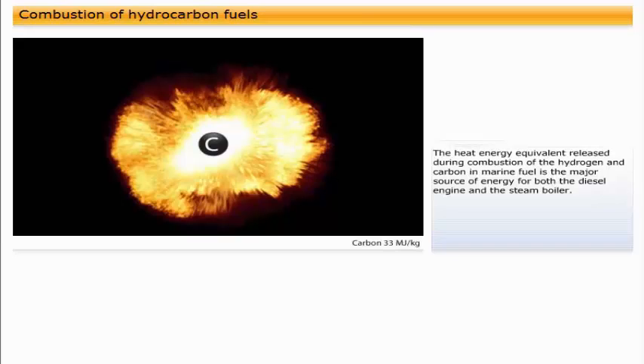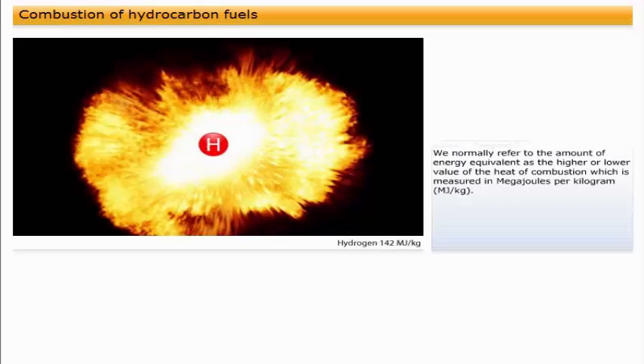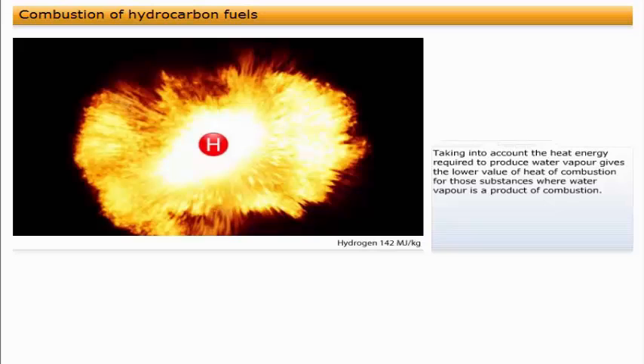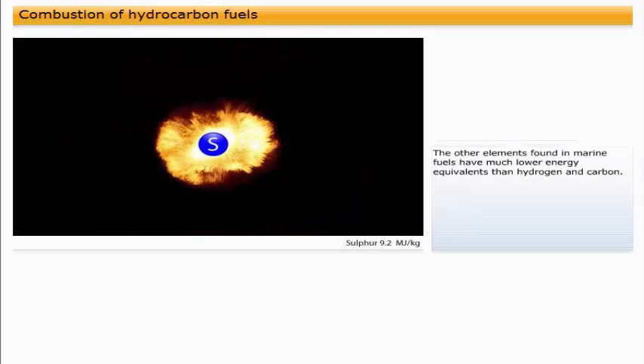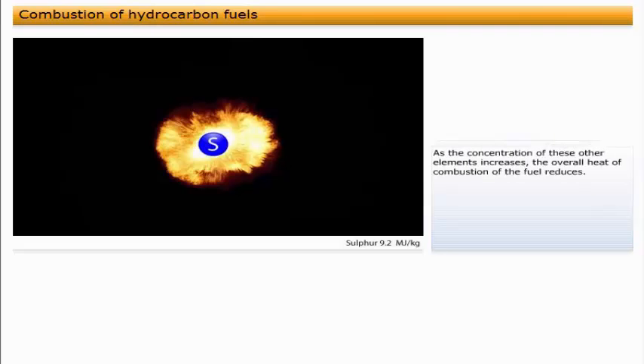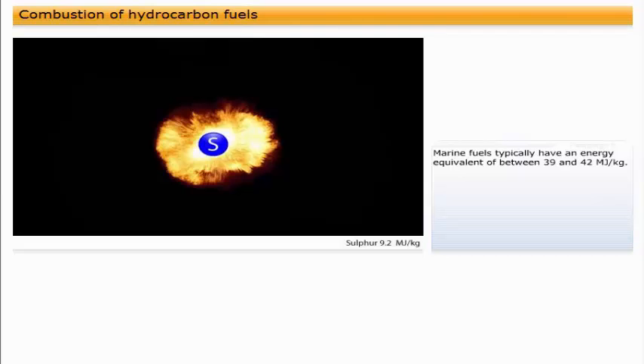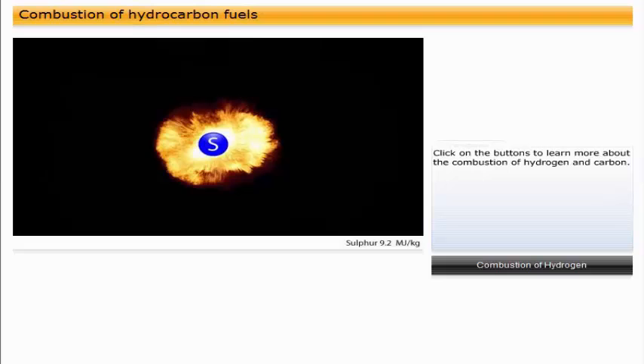The heat energy equivalent released during combustion of the hydrogen and carbon in marine fuel is the major source of energy for both the diesel engine and the steam boiler. We normally refer to the amount of energy equivalent as the higher or lower value of the heat of combustion, which is measured in megajoules per kilogram. Taking into account the heat energy required to produce water vapor gives the lower value of heat of combustion for those substances where water vapor is a product of combustion. The other elements found in marine fuels have much lower energy equivalents than hydrogen and carbon. As the concentration of these other elements increases, the overall heat of combustion of the fuel reduces. Marine fuels typically have an energy equivalent of between 39 and 42 megajoules per kilogram.